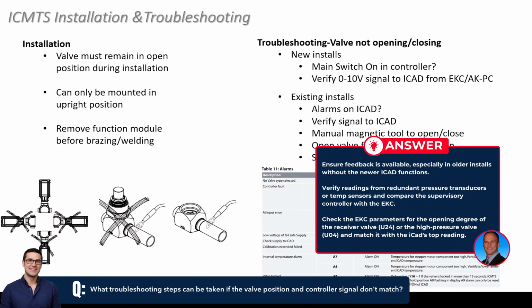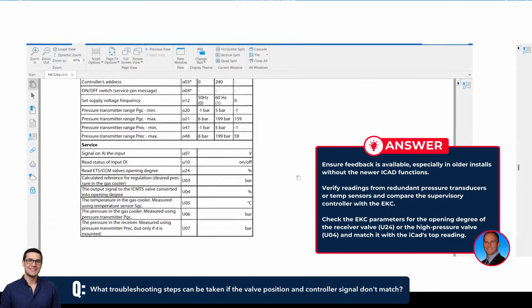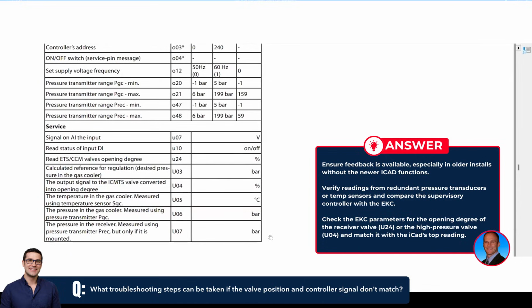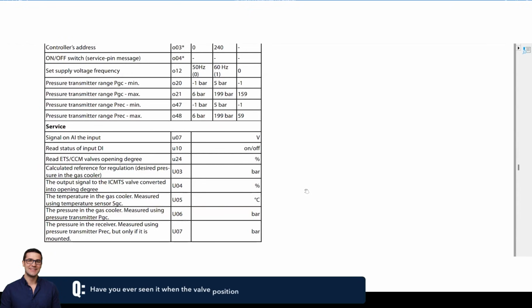But then otherwise, it's really getting back into the EKC parameters and looking at these U settings to either check that opening degree of the receiver valve on U24, or the high pressure valve for the ICMTS would be U04. We go to that setting in the EKC, and that should give us an opening degree percentage for the ICMTS in particular, that we could then turn around and look at the top of the ICAD and see if it's the same opening degree there. That should match. Have you ever seen it when it's different?